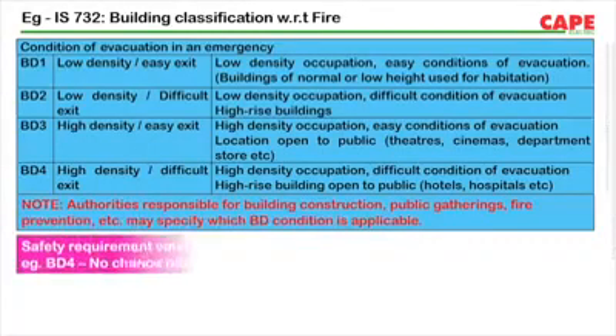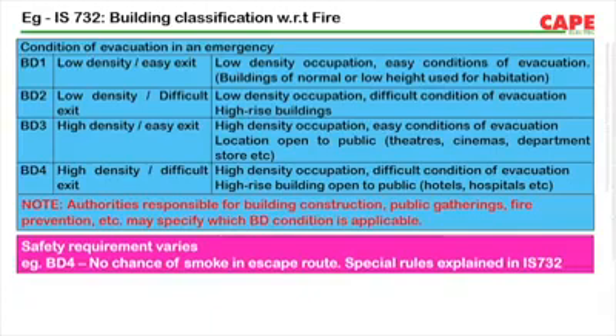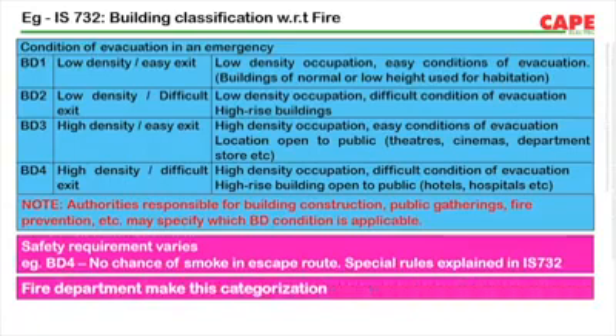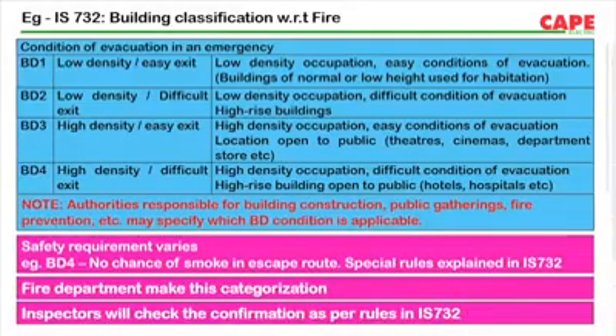Now what is important is the note under this category. The note says, authority responsible for building construction, such as fire and rescue department, shall make this categorization. Type of wiring to be adopted, especially in the escape route, varies depending upon the building category. The concept followed is, fire safety department shall make the building categorization and electrical inspectors shall ensure wiring conformation based on the rules for each category as per IS 732. This is an easy way of handling responsibilities by the appropriate government bodies.